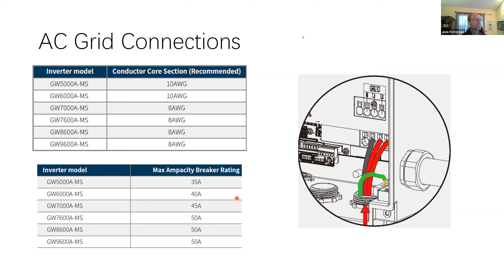For the PV, it's pretty easy. You're just going to set the right grid type, 240 volt. There are a couple choices because, for example, California has some utilities with specific settings, so you can choose those specifically. Most people will choose the IEEE 1547 240. Once you've done that, you're generally done with the PV in terms of getting the inverter commissioned so it can operate.